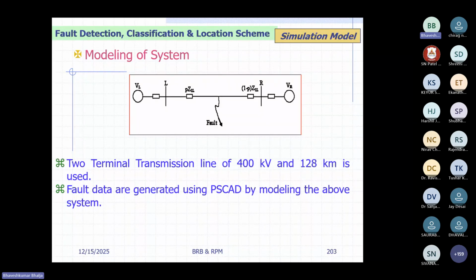Here I have shown you a simple two terminal transmission line at 400 kV. It is a 128-kilometer line. This is a standard line used by a utility in our country, used by GETCO only. The fault data you can generate using any tool. You can use PSCAD, MATLAB, or any other software like dSPACE or Typhoon, OPAL-RT, RTDS, a microcontroller box, anything. Any simulation network, EMTP, ETAP, anything you can use for modeling purposes.